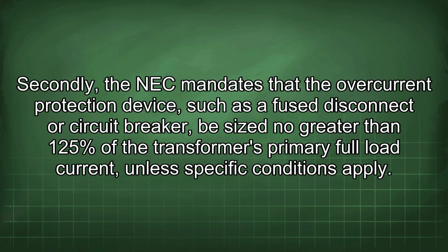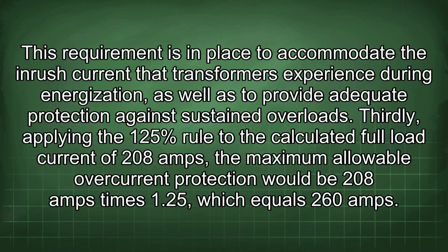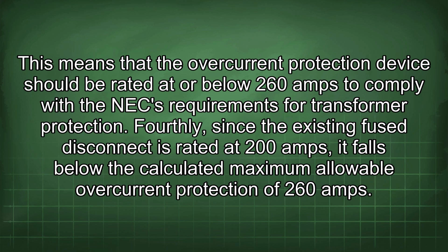Secondly, the NEC mandates that the overcurrent protection device, such as a fused disconnect or circuit breaker, be sized no greater than 125% of the transformer's primary full load current, unless specific conditions apply. This requirement is in place to accommodate the inrush current that transformers experience during energization, as well as to provide adequate protection against sustained overloads. Thirdly, applying the 125% rule to the calculated full load current of 208 amps, the maximum allowable overcurrent protection would be 208 amps times 1.25, which equals 260 amps.